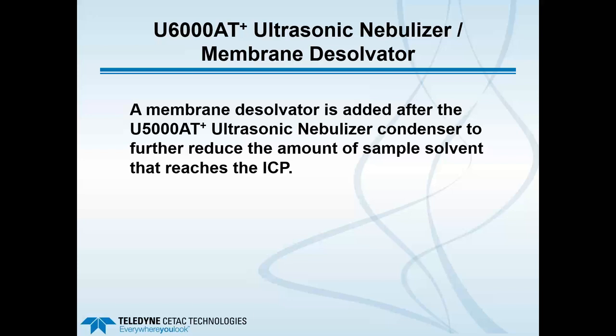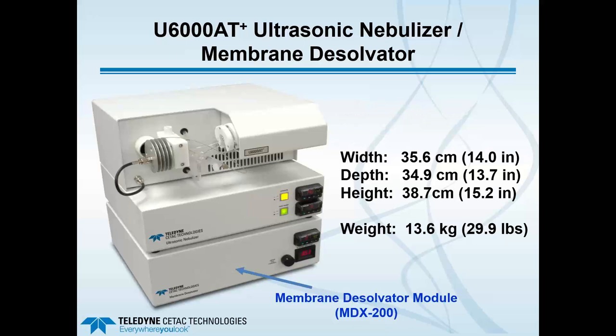With the ultrasonic nebulizer, we're going to add another component to it, changing the designation from U5000 to U6000. We add a membrane desolvator directly after the ultrasonic nebulizer condenser, to further reduce the amount of sample solvent — in this case volatile organics — that reaches the ICP. This is what the system looks like: it is a stackable module, meaning the ultrasonic nebulizer simply sits right on top of it, so the footprint remains the same. The height simply increases, and the combination of the two systems is designated as the U6000.